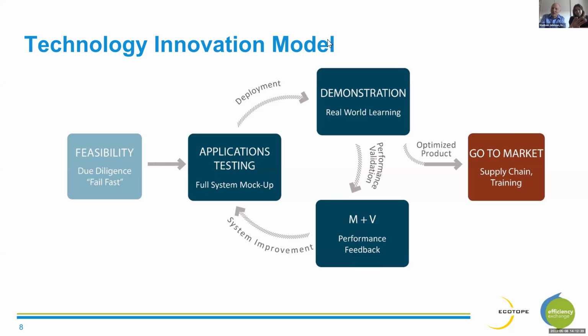So it starts with a feasibility study, which is kind of an engineering due diligence study on paper, to try to figure out where this technology might fail in the marketplace and address those before you try to bring it into a demonstration. And then also before you do a demonstration, we're starting with a heat pump technology, but there's a lot more to making a heat pump work in a building than just a good, well-designed heat pump. It's really part of an overall system that includes the storage tanks, the controls, the tempering valve, it's really a fully engineered system that has to be developed.